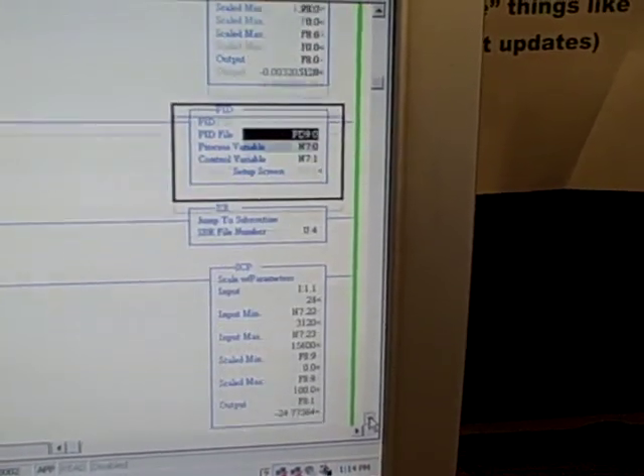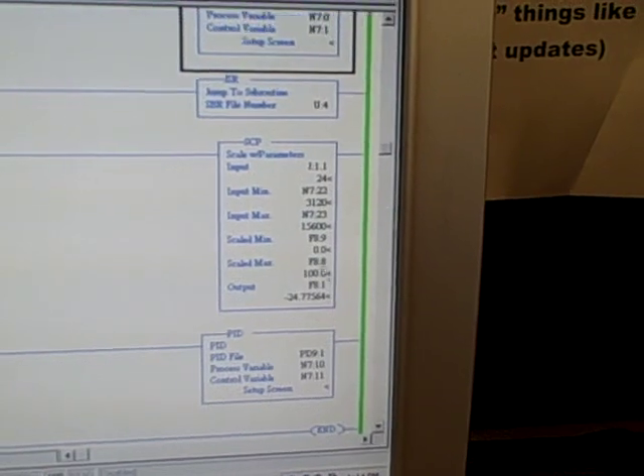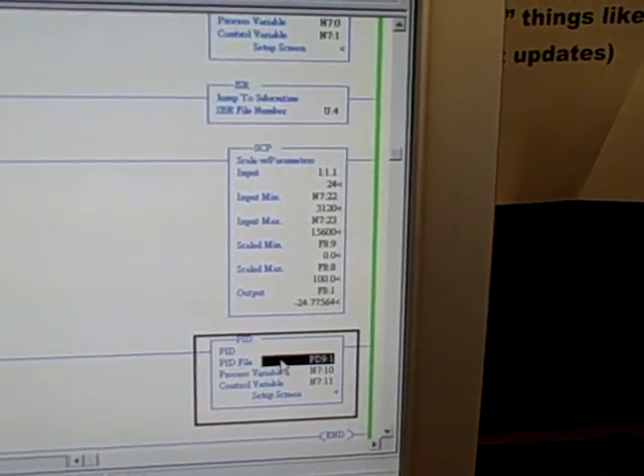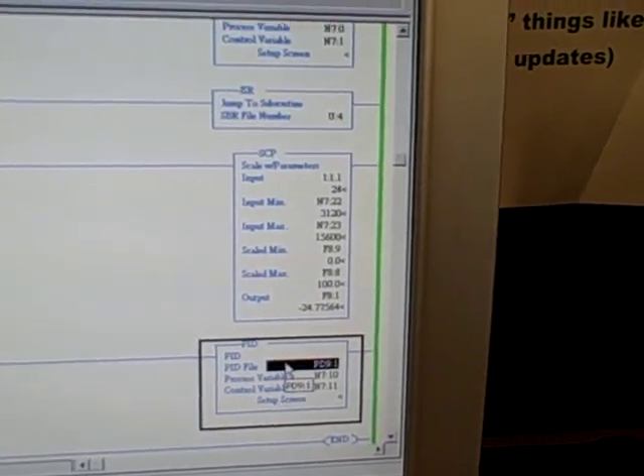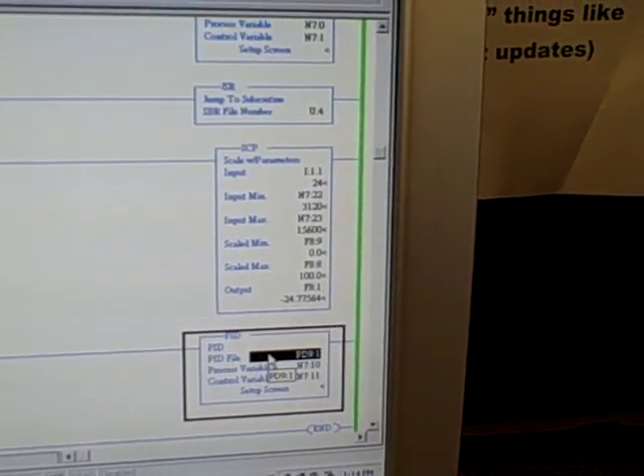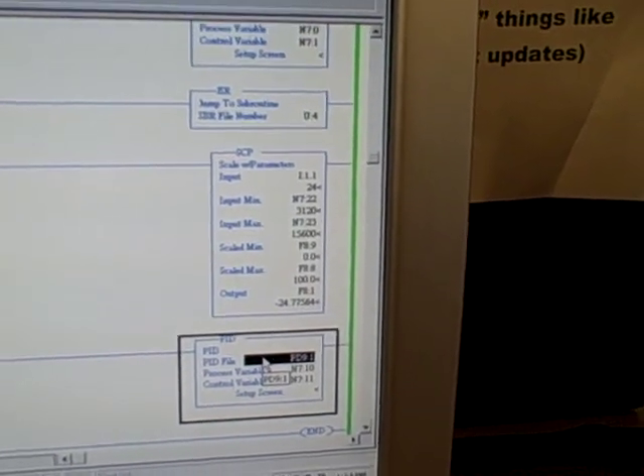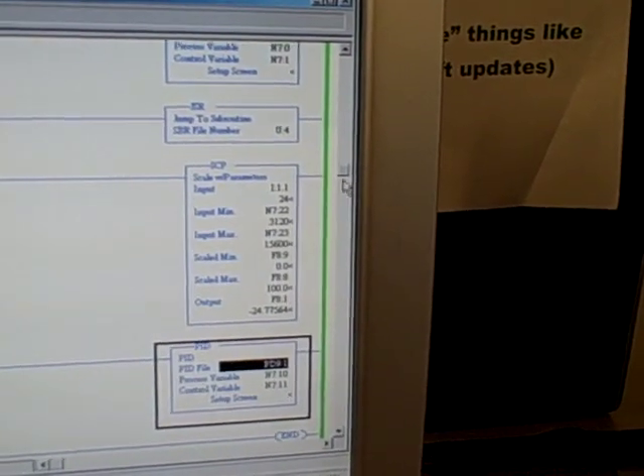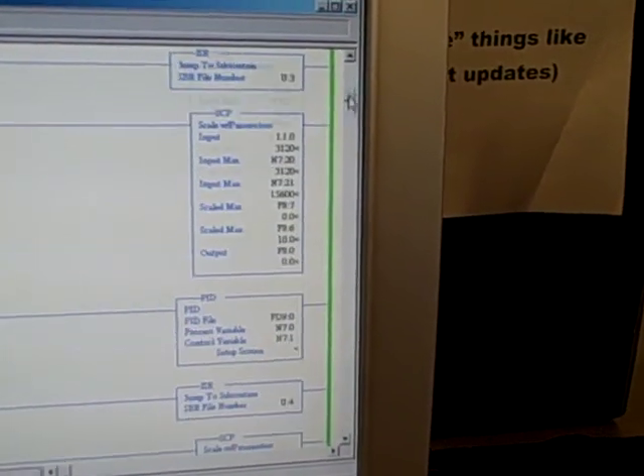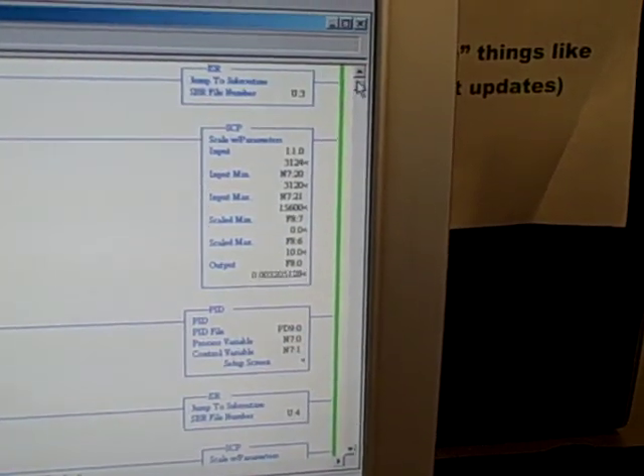Then we've got another jump to subroutine, another scale parameter, and another PID instruction. That's for the second loop in that same PLC. So each PLC can actually support two PID control loops.